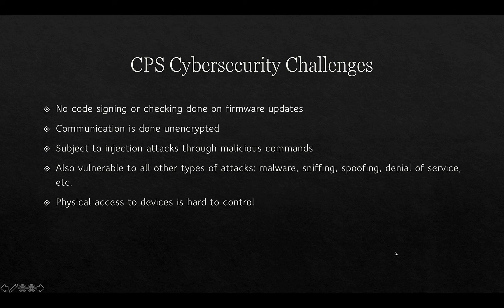Updating firmware in this environment is open to exploitation, as there is no code signing or checking done on much of the firmware that updates these systems. Communication is unencrypted and subject to injection attacks through malicious commands, and also vulnerable to malware, sniffing, spoofing, and denial of service attacks. Physical access to devices is also hard to control — for example, valves on a remote pipeline are difficult even for operators to visit and update, let alone protect from malevolent parties or from damage caused by animals and weather.